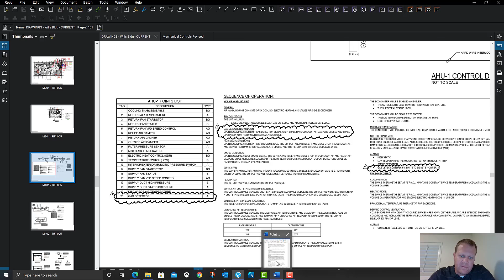The point to point is part of the commissioning process, and it would be part of, probably in my mind, the pre-functional test plan, because it's the functional test plan, FTP, that is usually the last thing. Functional test plan versus pre-functional test plan, anyway, there's a whole bunch of layers to commissioning, and like I said, the last one is to make sure the entire system seems to be working and functioning. But one of the steps is the point to point that we are talking about. One of the steps to get to that point, to make sure that it is all working, is to check out all these points.